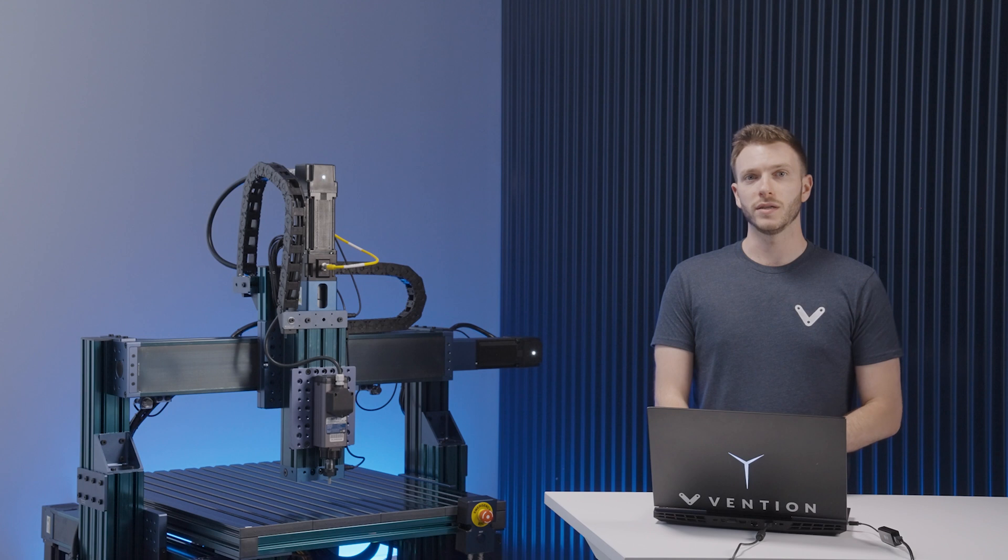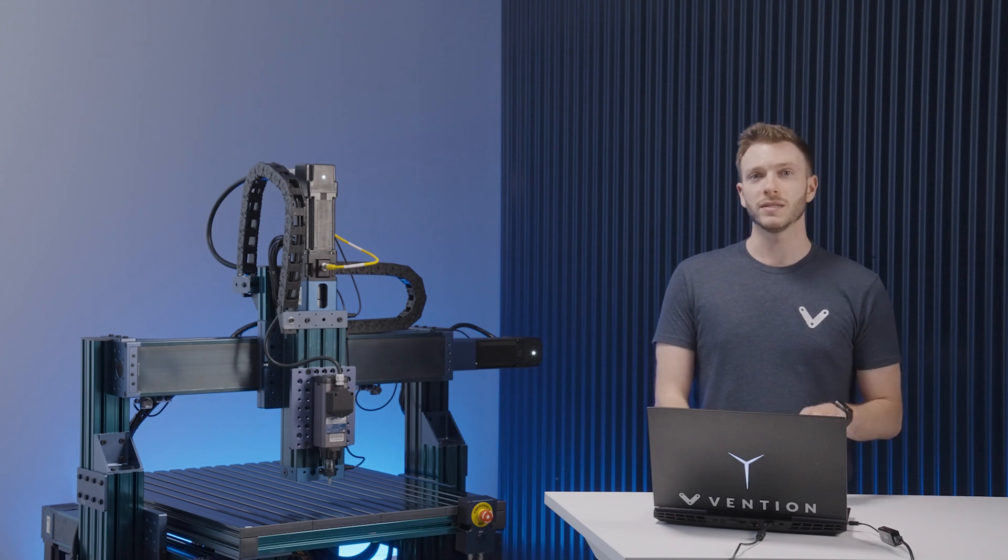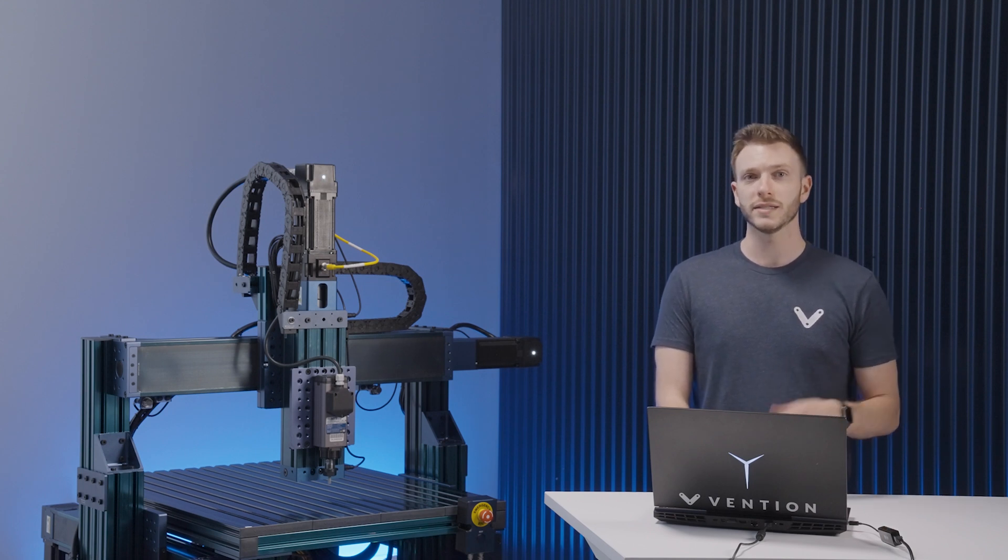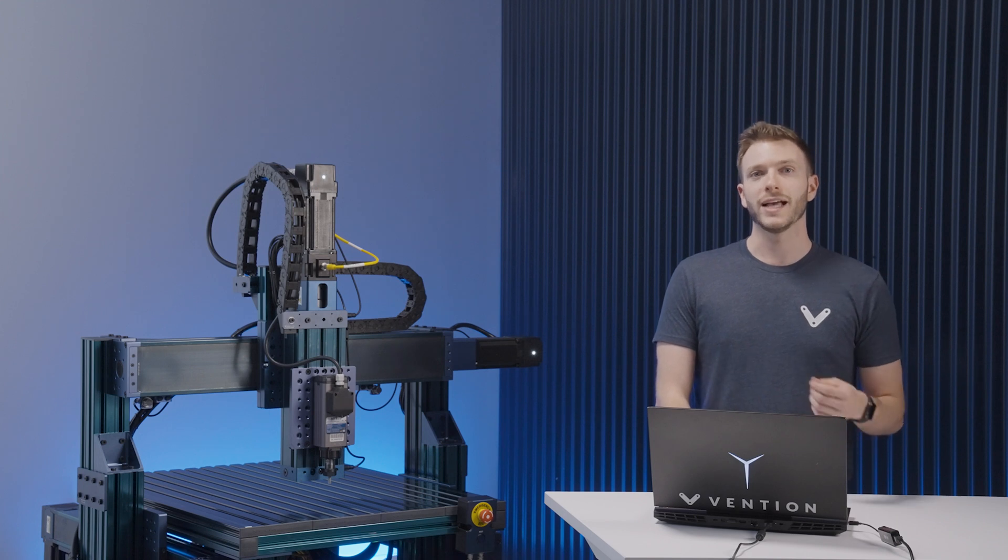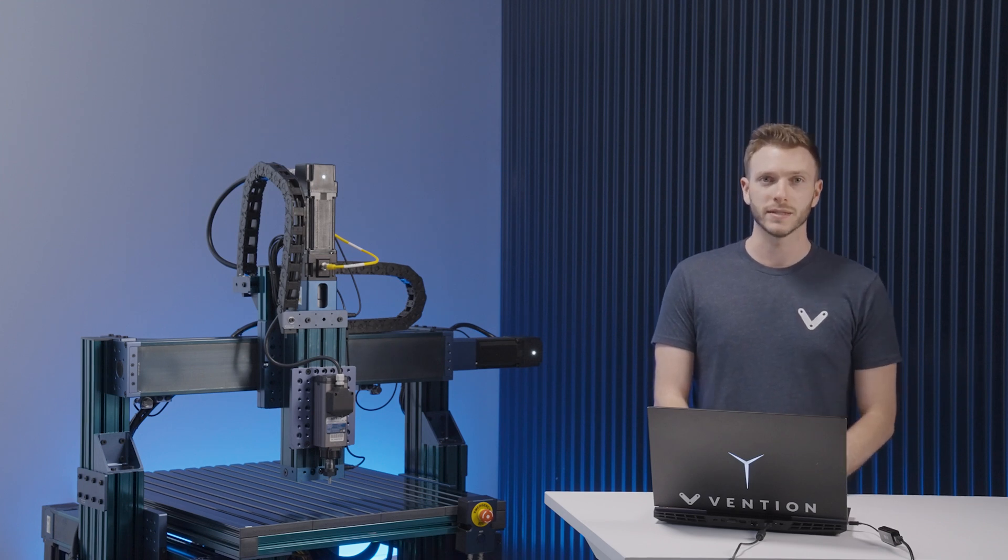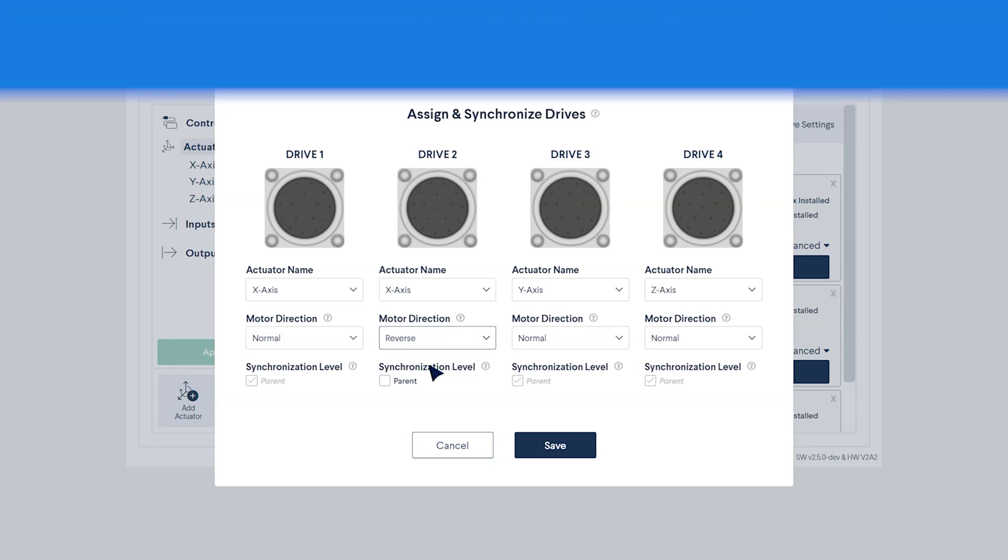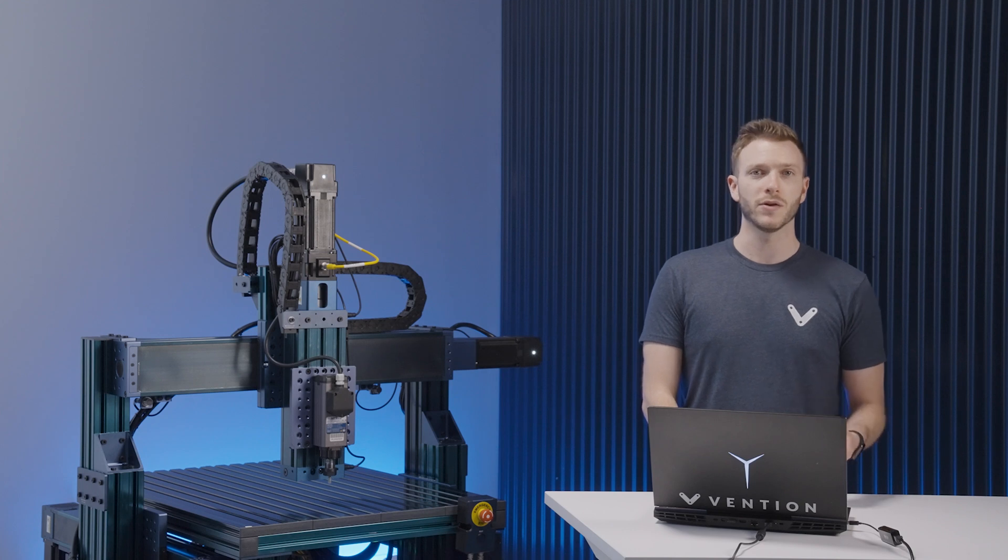It should be noted that the two drives that you are syncing must have the exact same mechanical setup in terms of motor size, actuator type and length, as well as if there is a gearbox or power-off brake present. We recommend double-checking your automation diagram to ensure that the motor direction is correct, as it's common to see two synced motors that rotate in opposite directions.